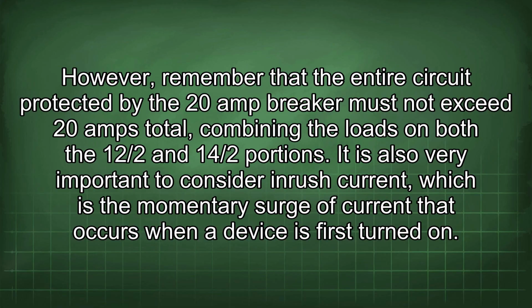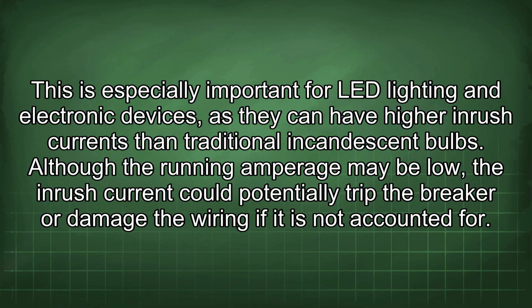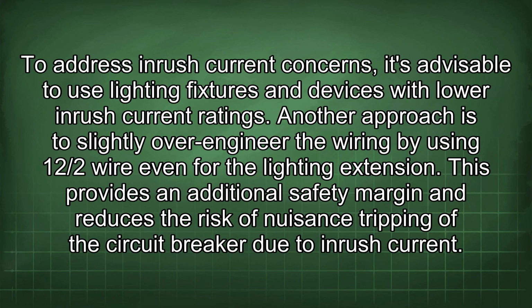It is also very important to consider inrush current, which is the momentary surge of current that occurs when a device is first turned on. This is especially important for LED lighting and electronic devices, as they can have higher inrush currents than traditional incandescent bulbs. Although the running amperage may be low, the inrush current could potentially trip the breaker or damage the wiring if it is not accounted for. To address inrush current concerns, it's advisable to use lighting fixtures and devices with lower inrush current ratings. Another approach is to slightly over-engineer the wiring by using 12/2 wire even for the lighting extension. This provides an additional safety margin and reduces the risk of nuisance tripping of the circuit breaker due to inrush current.